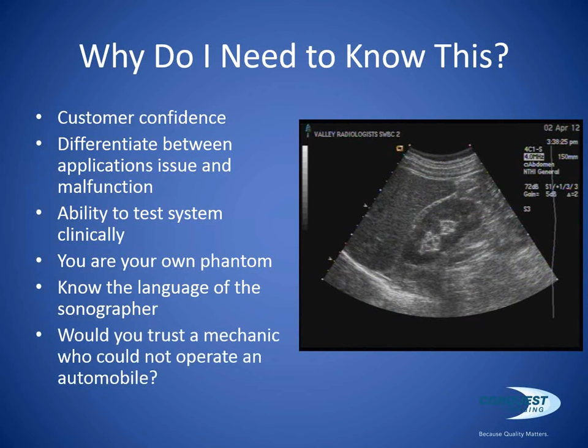The first thing we want to do is evaluate the monitor display settings. If the system main display is not set properly, everything else is pretty much going to be skewed. And so when evaluating system image quality, you want to ensure that the monitor or main display, whether it's a CRT or an LCD, is set properly.